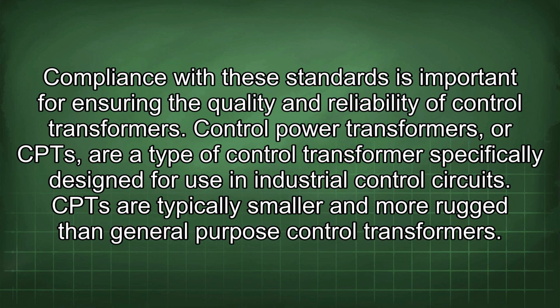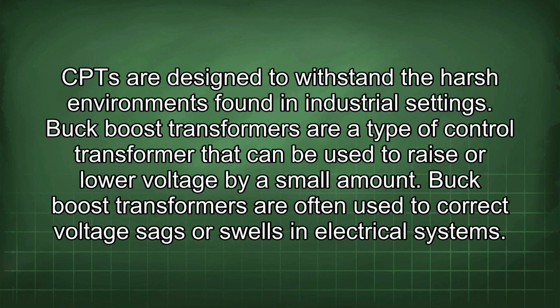Control power transformers, or CPTs, are a type of control transformer specifically designed for use in industrial control circuits. CPTs are typically smaller and more rugged than general-purpose control transformers. CPTs are designed to withstand the harsh environments found in industrial settings. Buck-boost transformers are a type of control transformer that can be used to raise or lower voltage by a small amount. Buck-boost transformers are often used to correct voltage sags or swells in electrical systems.